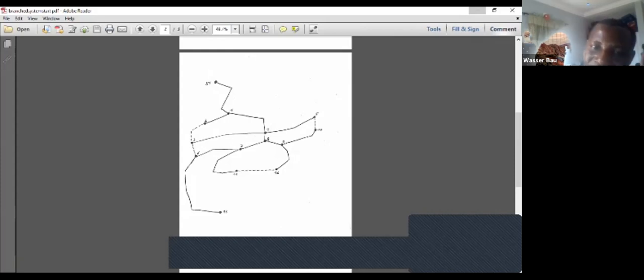So this is not a computer model. So here I will run it. Because I didn't use exact value, it's still giving me negative pressure. It means water is not flowing somewhere. Diameter is 150, diameter is 125, diameter is 80, diameter is 100, diameter is 80. So this guy is going to get 100. Let me put 80.